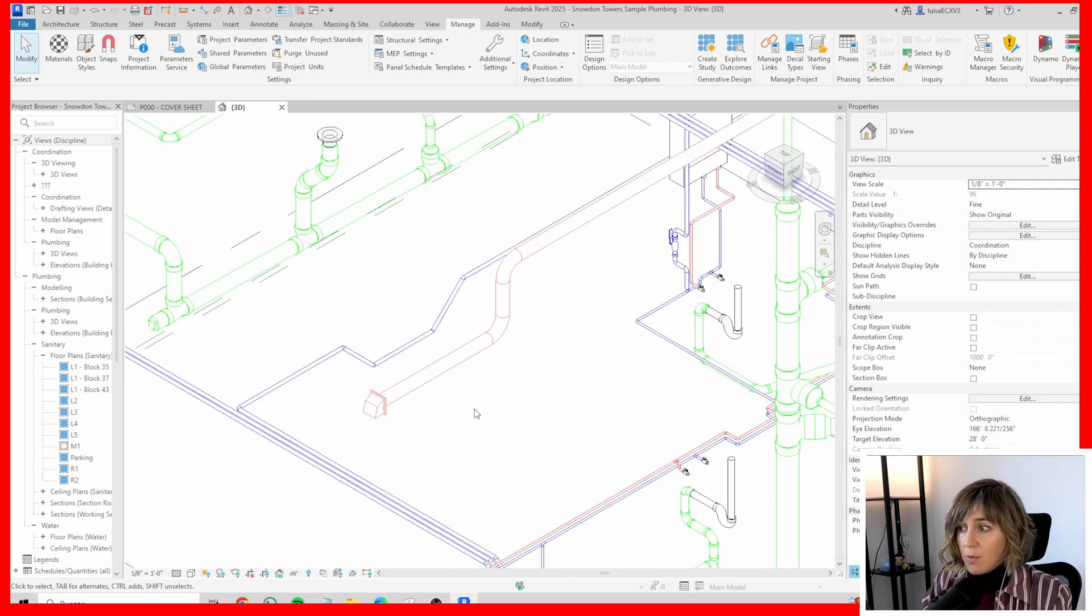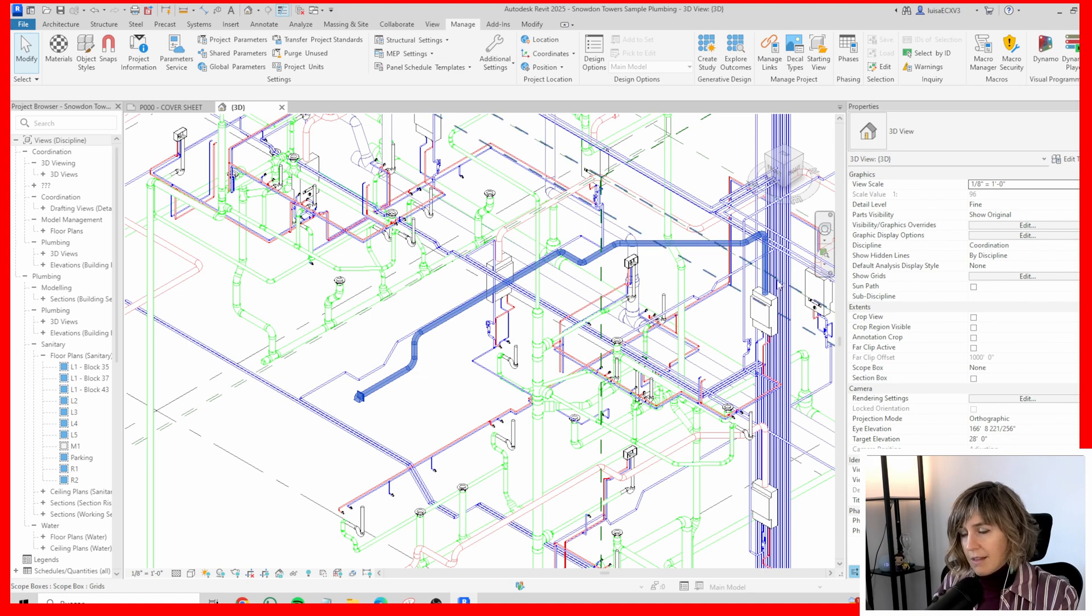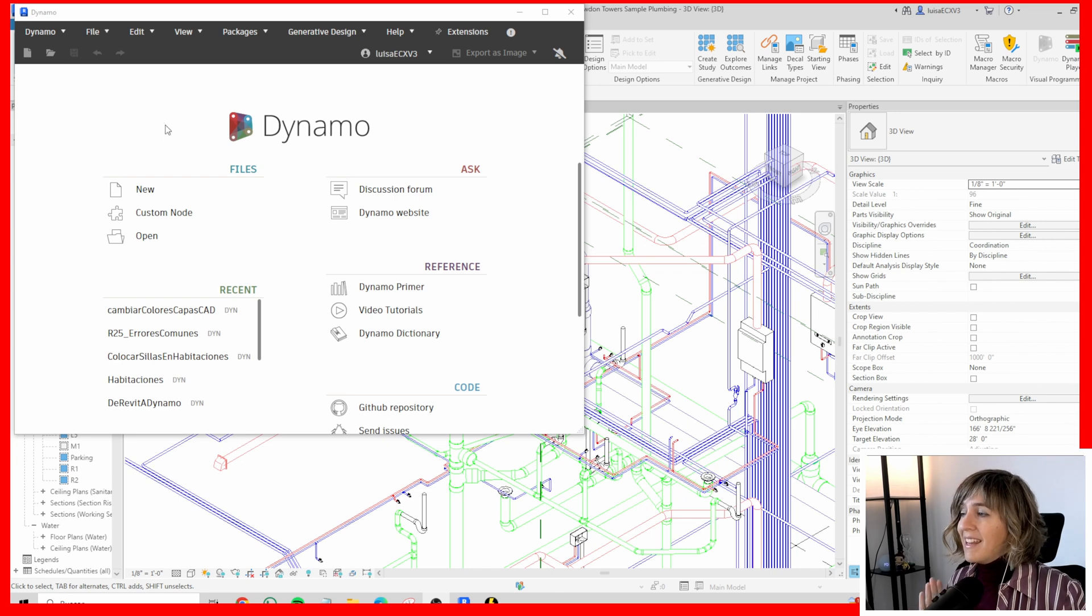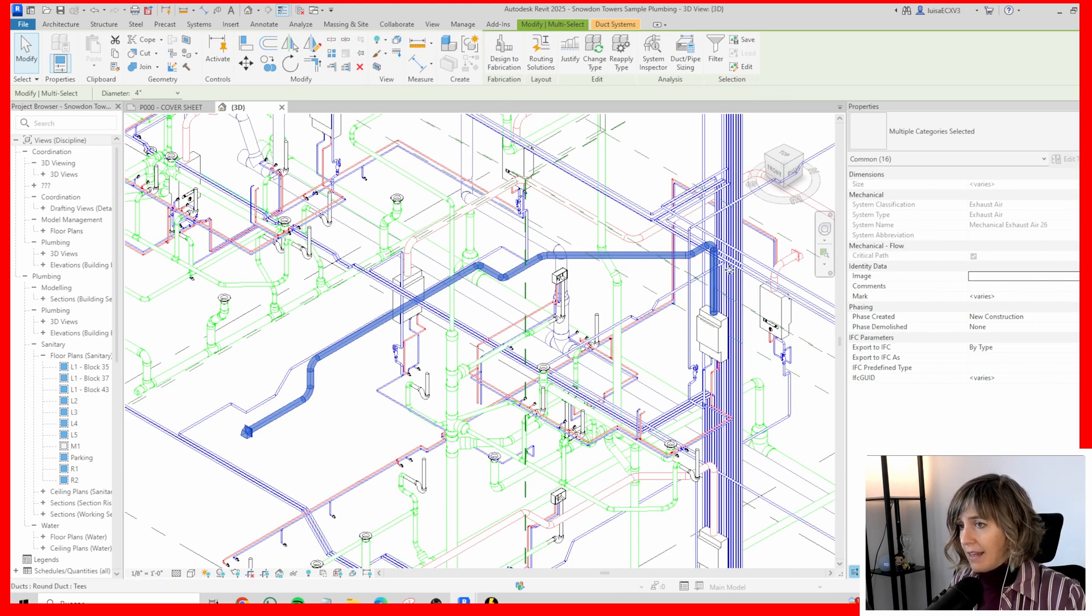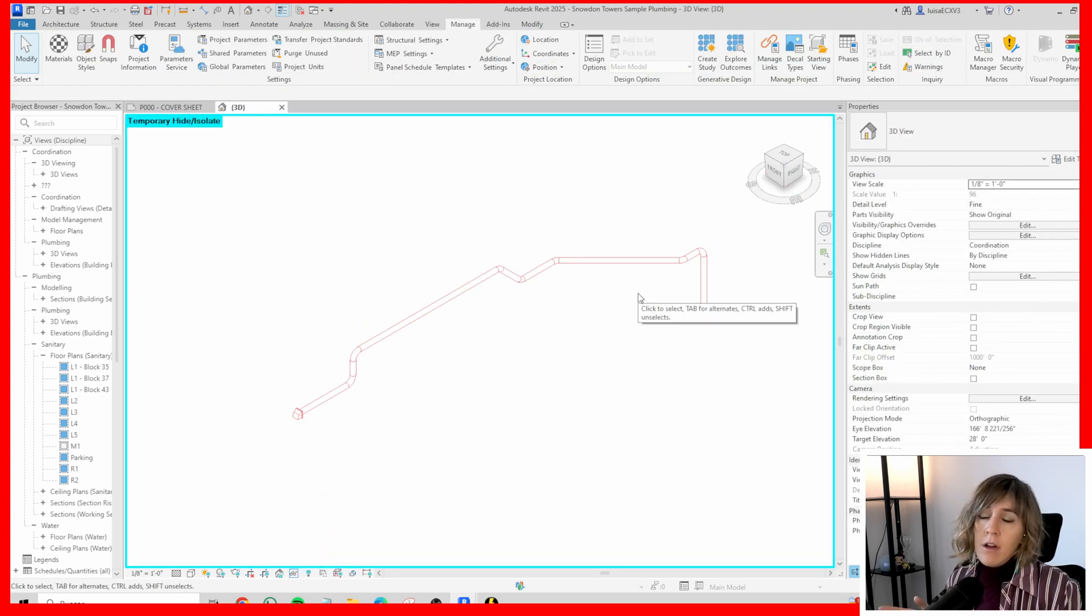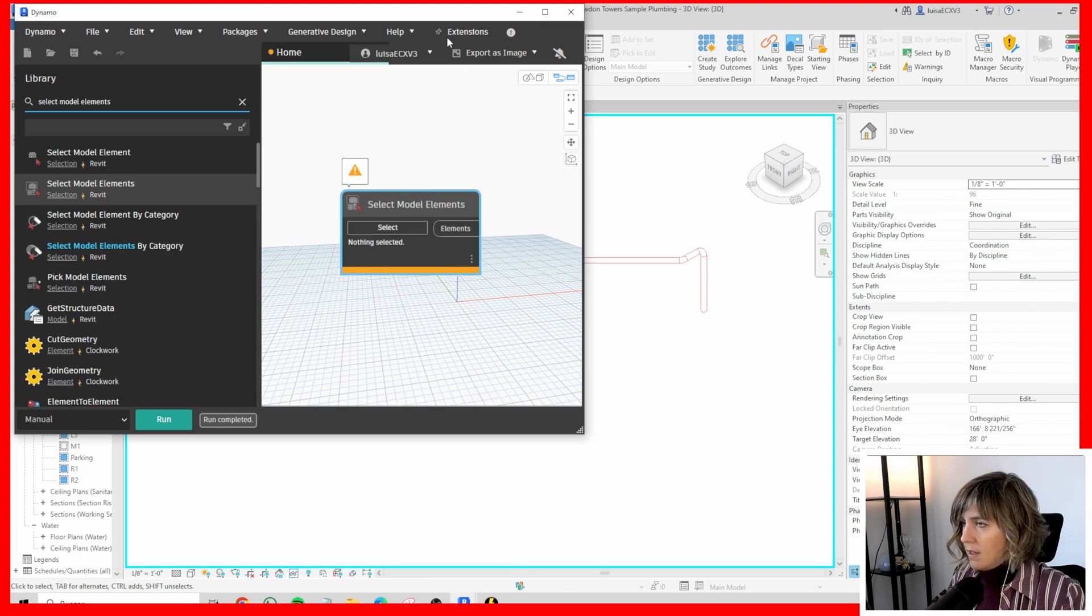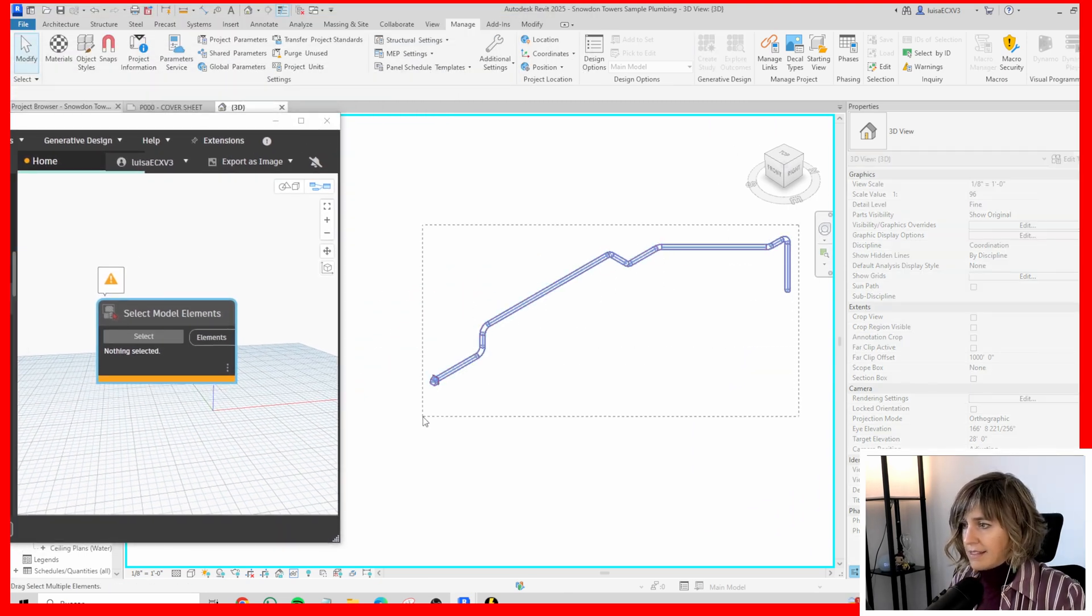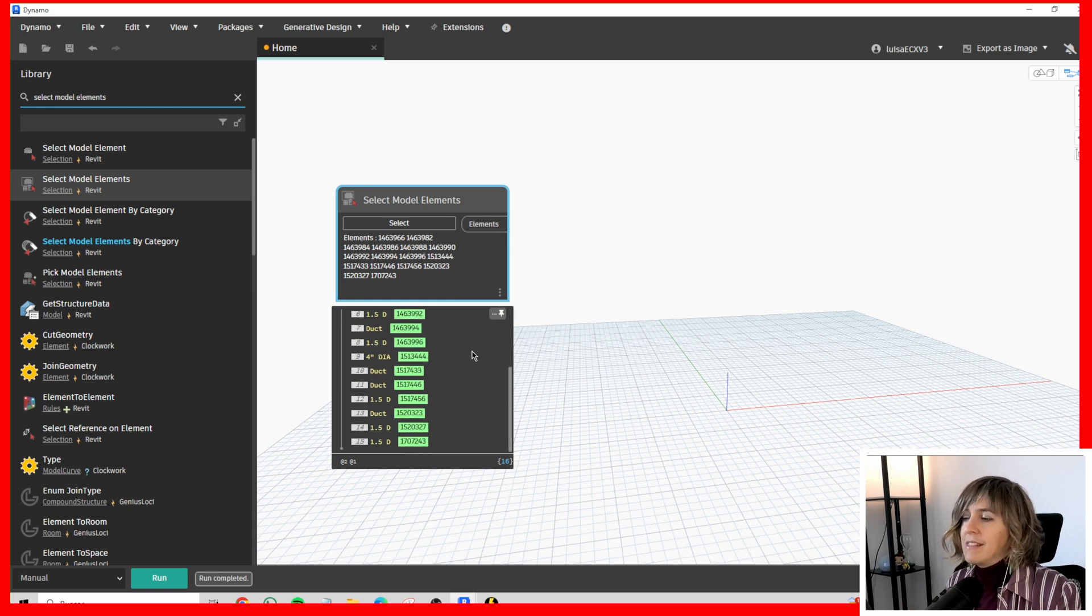I'm going to transmit to a parameter called total system length the whole length of this full system that I'm selecting right now. First, open Dynamo, of course. Opening a new Dynamo. The first thing that you may consider is, let's isolate these elements. I click the whole system, and then right here, I'm going to select isolate element. There I have only the elements I'm currently interested in. After that, I'm going to select these elements with select model elements. If I click run, I already know that I have all the elements in the system, and only those.